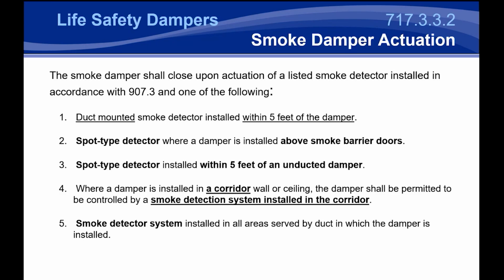Not only does it give the installer a little bit of leeway in how they're installing the product, there are electrical wiring diagrams and instructions on how to mount that from the manufacturer as well. And typically, if these are externally mounted to the sleeve, you can then have both the smoke detector and the actuator on the same side, which is not common, is not available for all damper sizes, and may not even be common for most applications. So having them shipped loose does give one other added benefit.